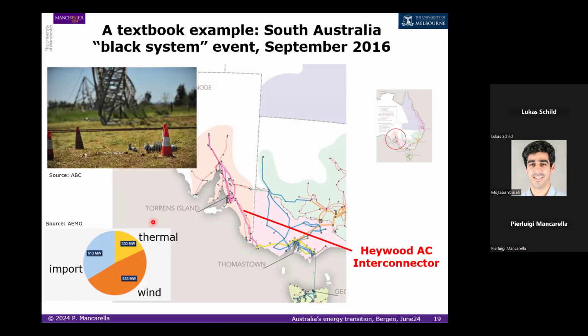When you lose lots of local generation, because of the physical laws, the power flows basically move across the interconnector. The interconnector got overloaded and also tripped. So when you trip the interconnector, this area of the grid becomes a physical island. But in this island, you only have very few synchronous machines to provide system stability, particularly frequency stability.